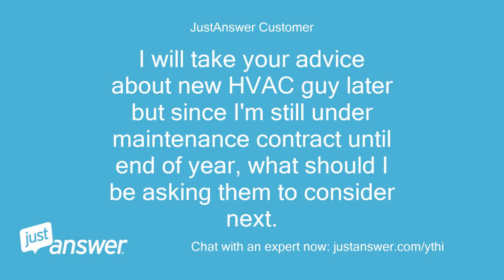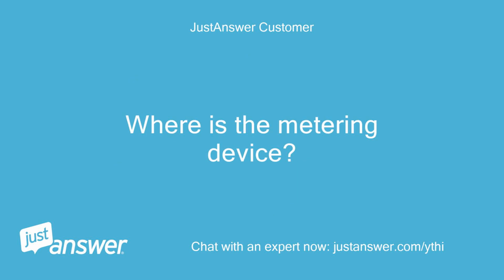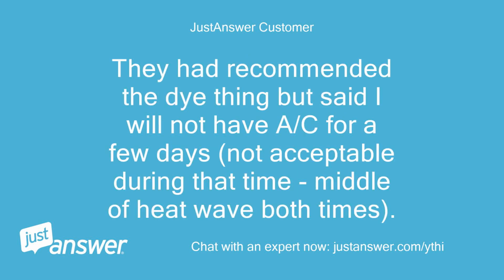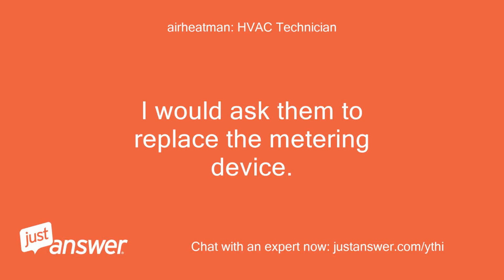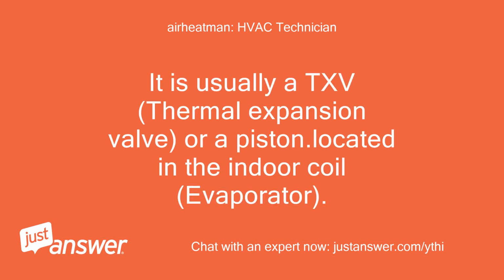I will take your advice about new HVAC guy later, but since I'm still under maintenance contract until end of year, what should I be asking them to consider next? Where is the metering device? They had recommended the dye thing but said I will not have AC for a few days, not acceptable during that time, middle of heat wave both times. I would ask them to replace the metering device. It is usually a TXV thermal expansion valve, or a piston located in the indoor coil evaporator.